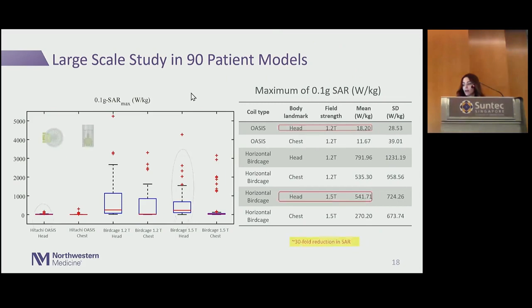compared to 1.5 Tesla horizontal system. The second question you might ask is, okay, if everything is so dependent on the relative position of the patient in the coil, what happens if you need to do an abdominal scan? What if I move the patient inside the coil? And that's what we did. The second thing we looked at was that, okay, let's move the patient. Let's look at the position when the chest is at the isocenter. Again, 23-fold reduction in the RF heating. So the advantage remains even when you move the patient.